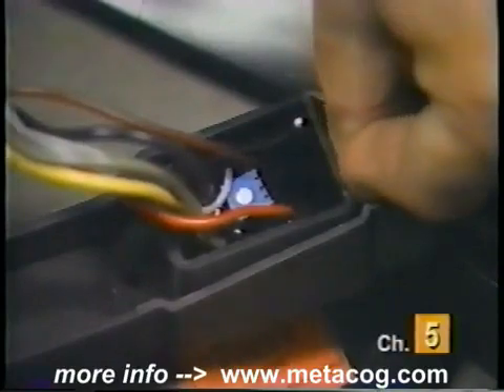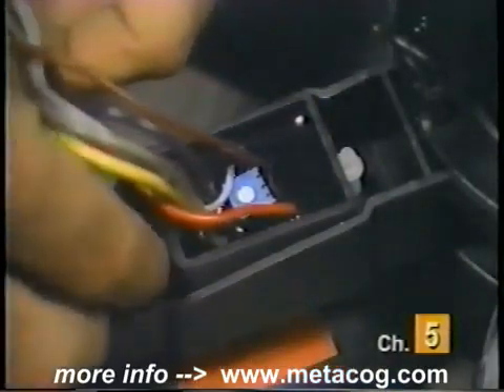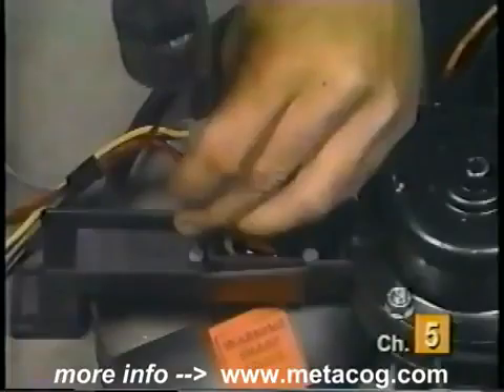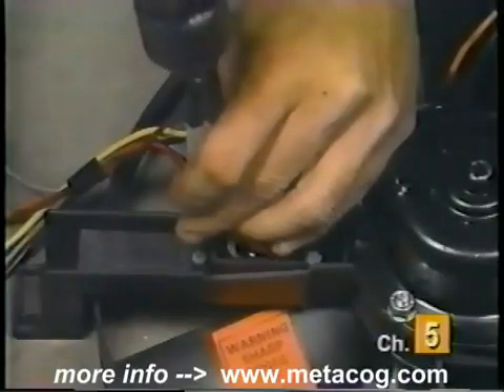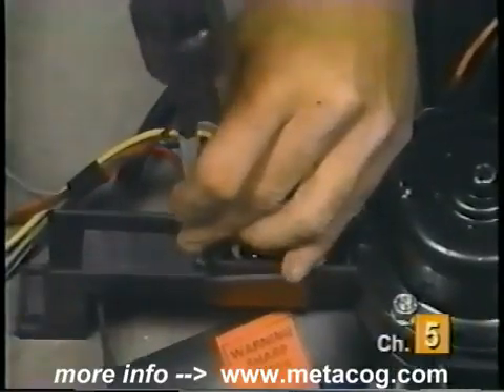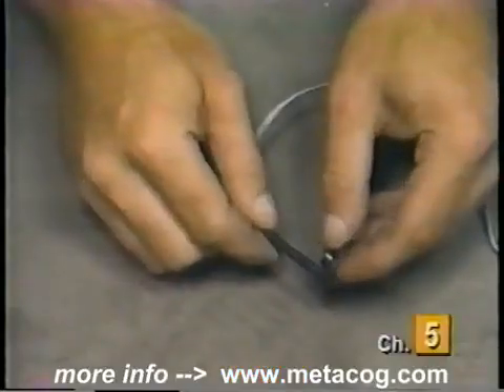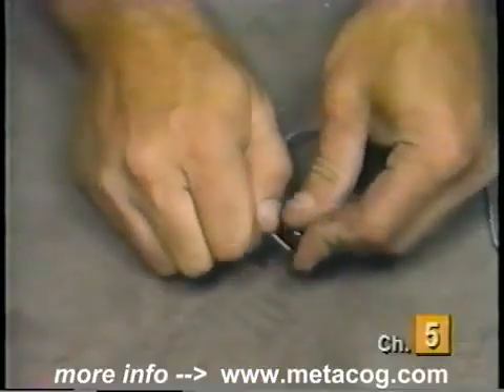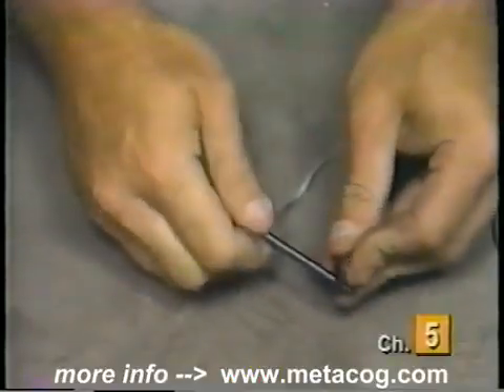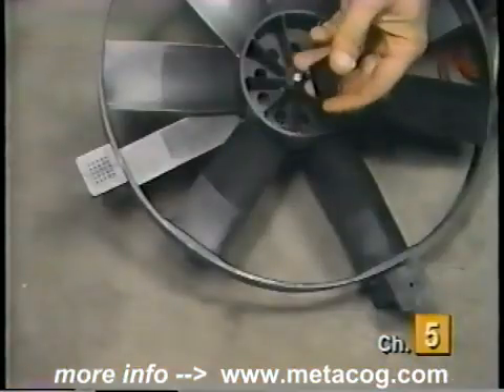Attach the control box to the mounting bracket with the plastic rivets supplied. Make sure the control box is mounted to allow access to the temperature adjusting screw. Press the rivets into the holes, and with a small punch and hammer, lightly tap the rivet center until it is flush with the rivet head. Insert the temperature probe through the mounting pad and button with the factory offset hole. You may need to enlarge the hole slightly with the screwdriver or punch to ease the installation of the probe.